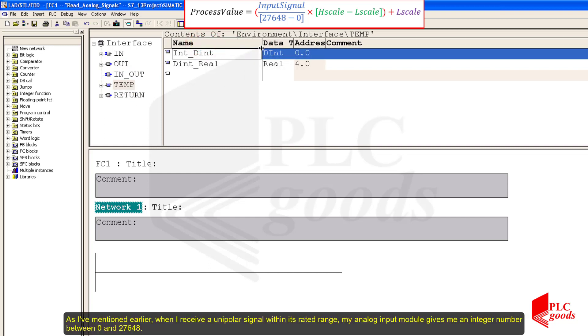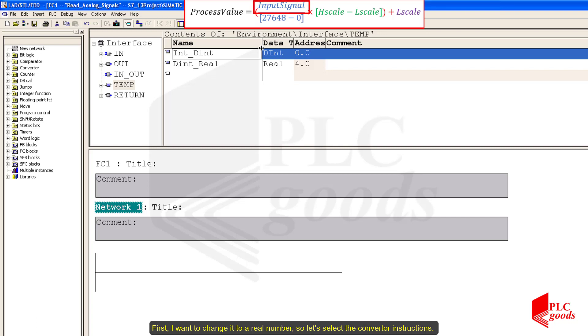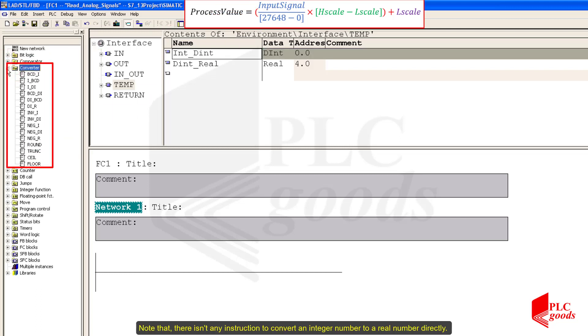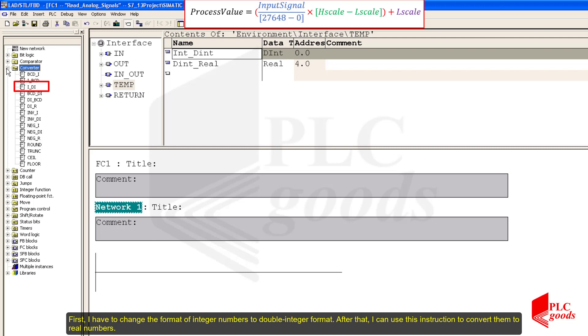When I receive a unipolar signal within its rated range, my analog input module gives me an integer number between 0 and 27648. First, I want to change it to a real number, so let's select the converter instructions. Note that there isn't any instruction to convert an integer number to a real number directly. First, I have to change the format of integer numbers to double integer format. After that, I can use this instruction to convert them to real numbers.